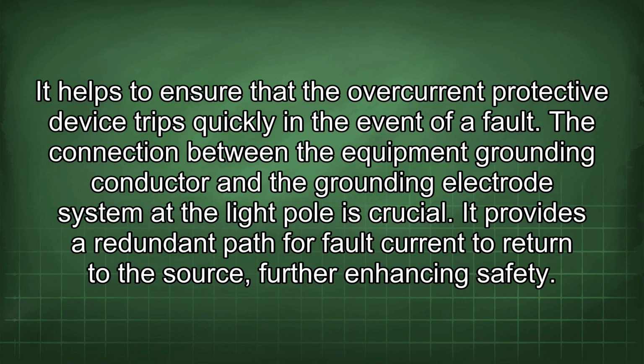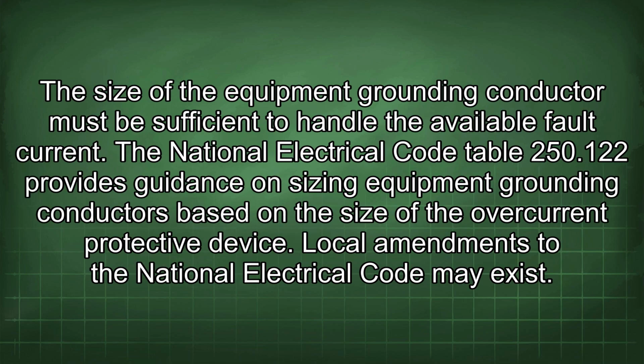The connection between the equipment grounding conductor and the grounding electrode system at the light pole is crucial. It provides a redundant path for fault current to return to the source, further enhancing safety. The size of the equipment grounding conductor must be sufficient to handle the available fault current. The National Electrical Code Table 250.122 provides guidance on sizing equipment grounding conductors based on the size of the overcurrent protective device.